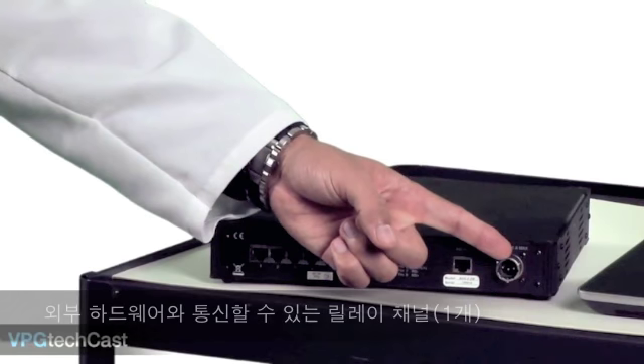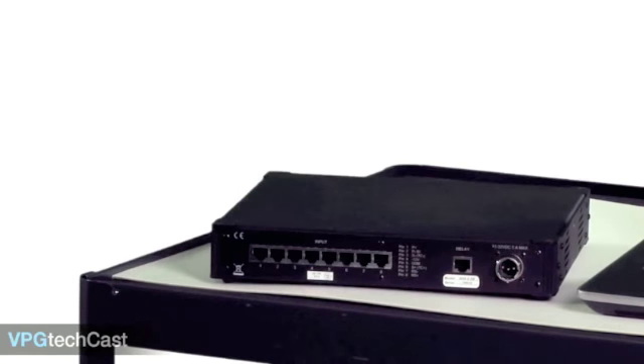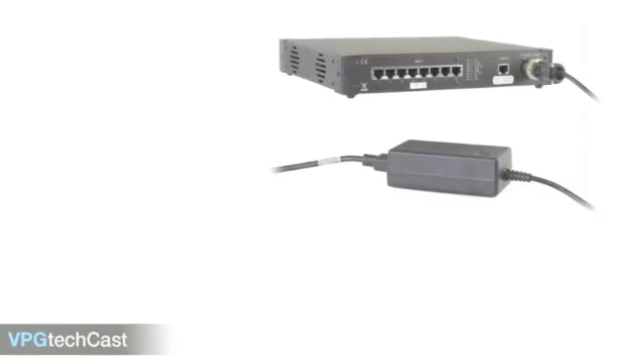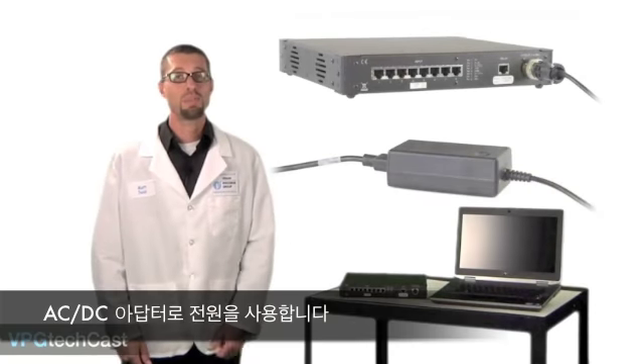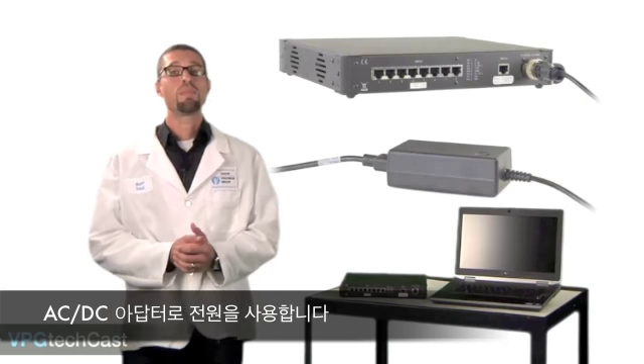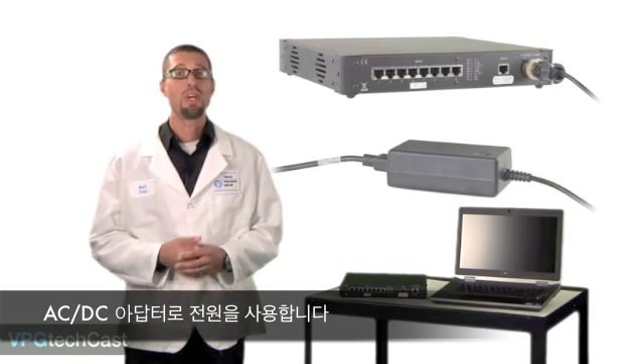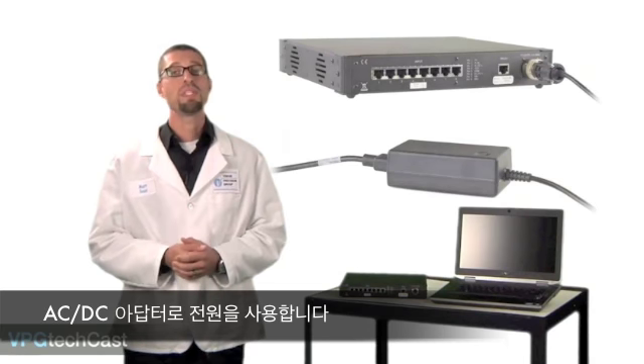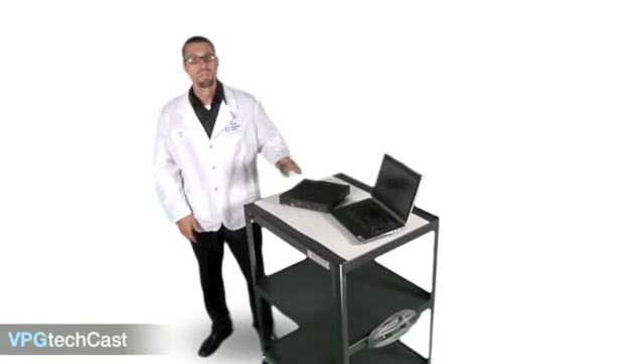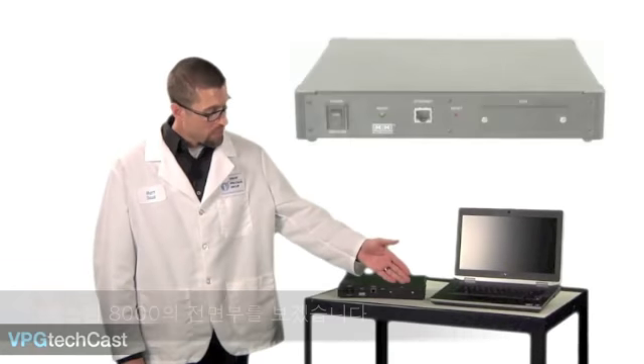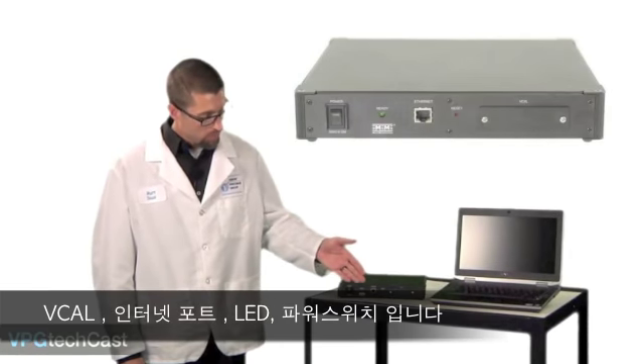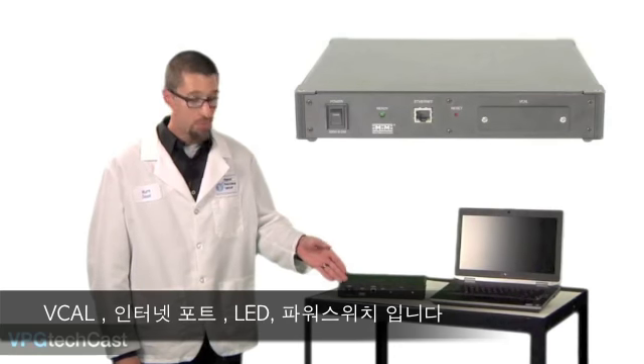Beside the external relay connection, you will find the DC power connector. The System 8000 is supplied with an AC-DC desktop switching power supply. It can also operate off of a battery or alternate DC power source, providing enough power can be supplied to meet the system and excitation power requirements. Now let's take a look at the front panel of the System 8000. Here we will find the VCAL and Ethernet input ports, the ready light, and the illuminated power switch.